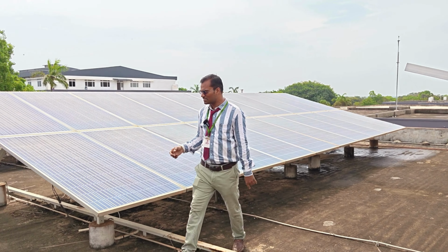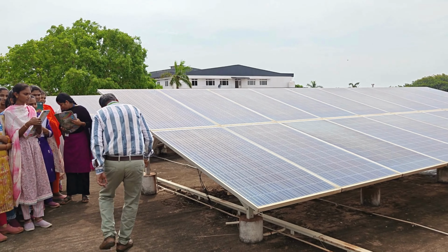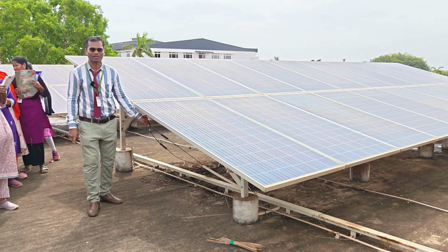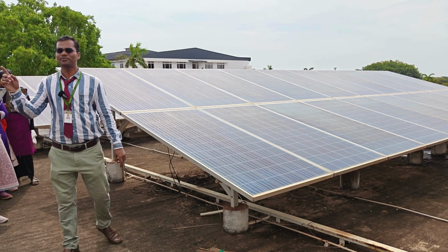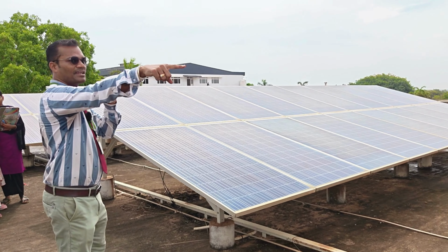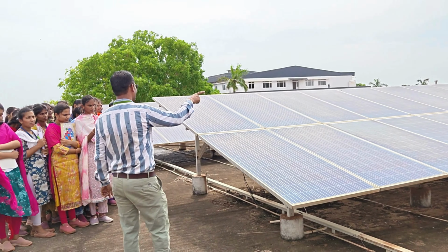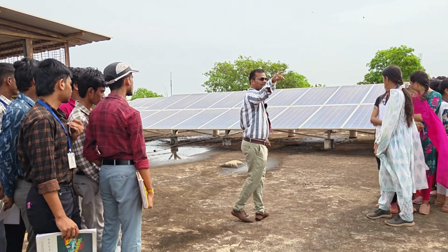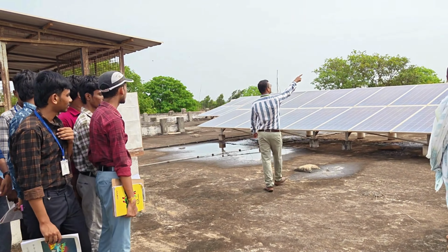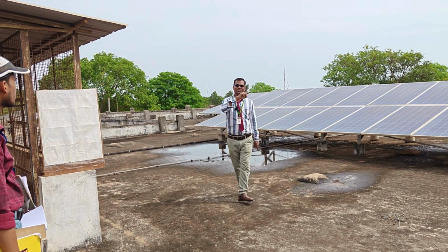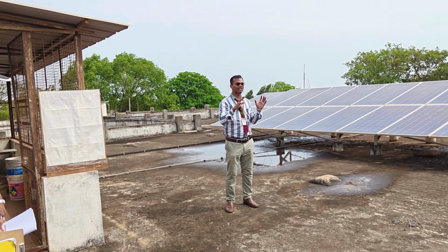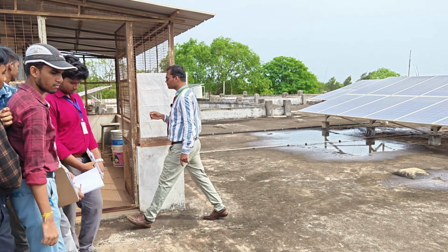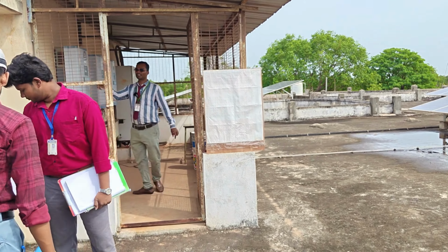When you connect them in series, this is how the 2 connections are connected. So these are the 2 resultant terminals you are going to get after connecting them. After connecting them like this, we are going to have 8 sets. So this is array 1 consisting of 20 panels. This is string 2 which consists of the remaining 20 panels. Like that you are going to have 8 arrays: array 1, array 2, array 3, array 4, array 5, array 6 and array 8. Like this you are going to have 8 arrays which will constitute a 50 kilowatt inverter. So here you can see, this is a grid connected inverter.